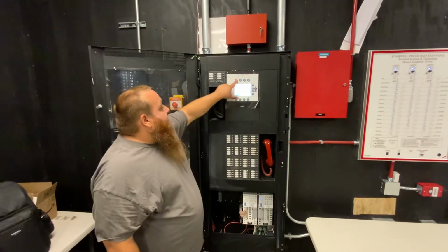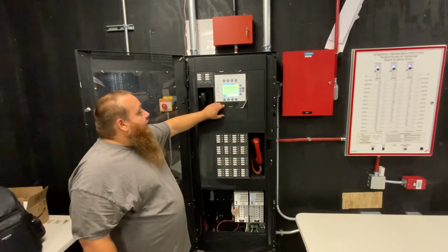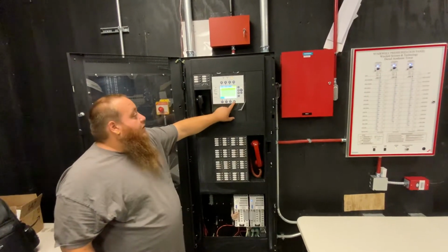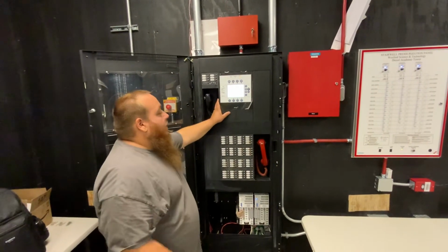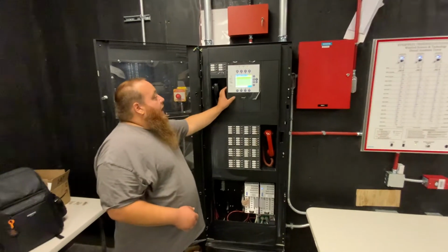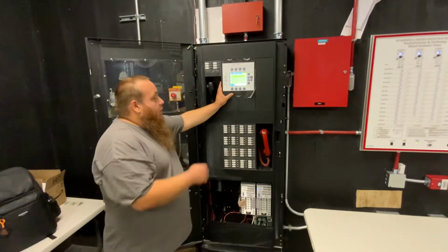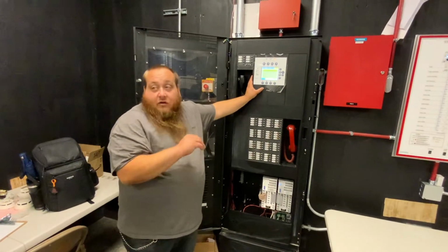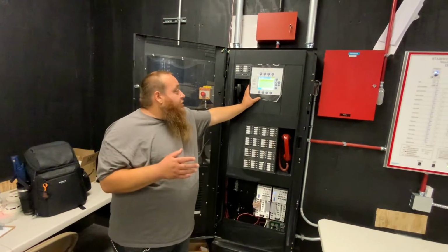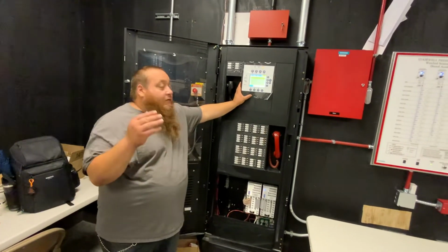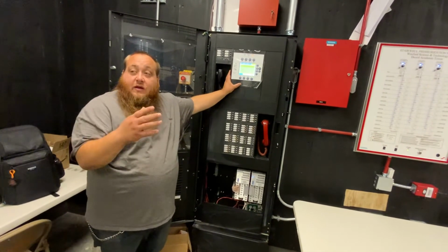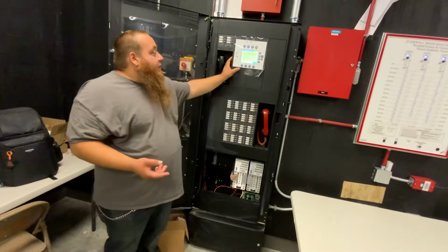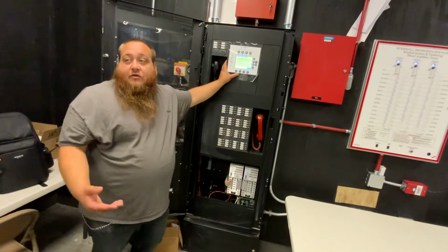Let's say there's a change of state. You still have to acknowledge it. Now it says out, meaning it disappeared. You reset. It's off the list. Anything that comes in and out of the system, you can reset it. As long as it says out, it's cleared. There is an option for self-restoring troubles, where if a trouble comes in and it clears, it'll automatically wipe off. But people like to see things come in and out so they know when things are clear.